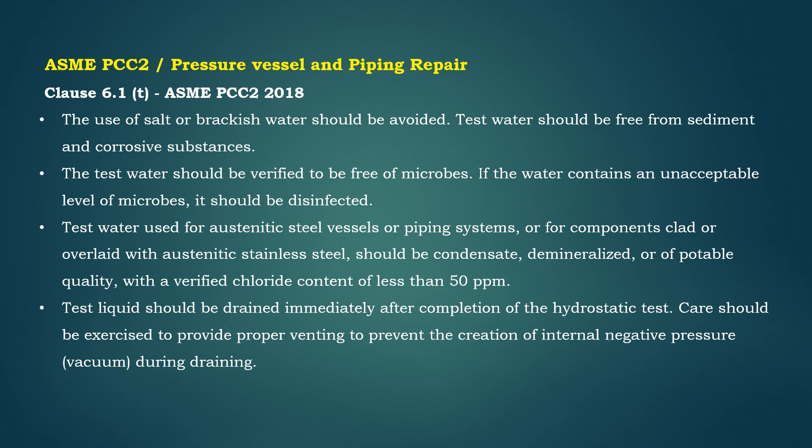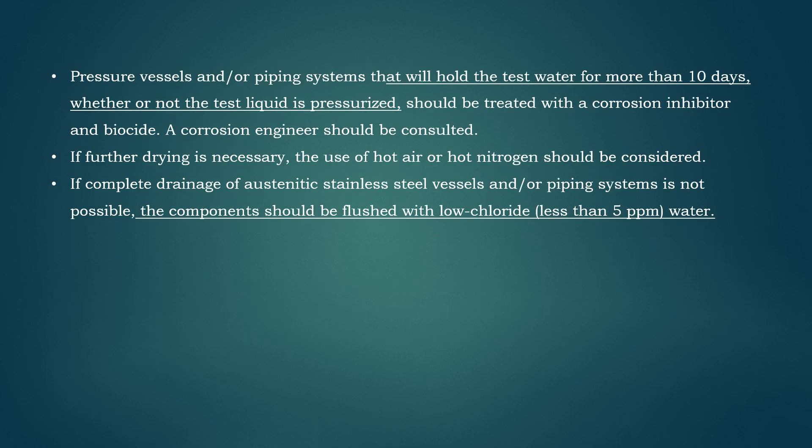Pressure vessels and/or piping systems that will hold the test water for more than 10 days — whether or not the test liquid is pressurized — should be treated with a corrosion inhibitor and biocide.